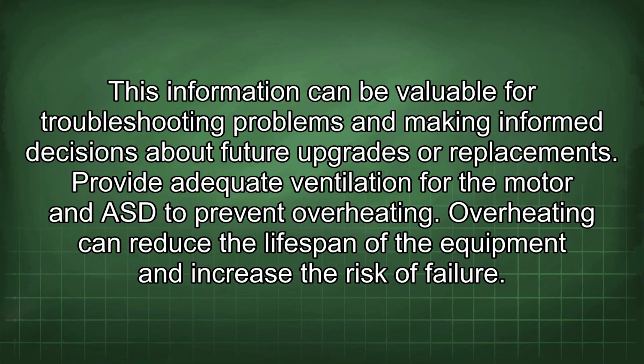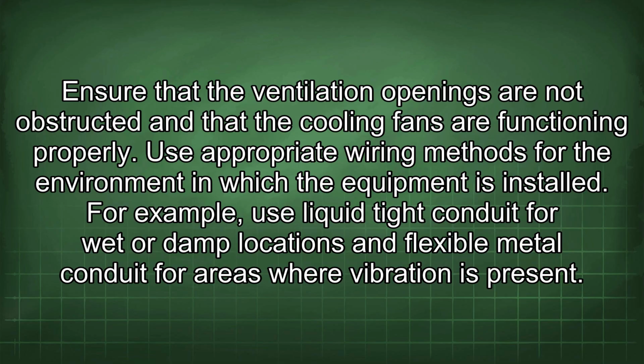Provide adequate ventilation for the motor and ASD to prevent overheating. Overheating can reduce the lifespan of the equipment and increase the risk of failure. Ensure that the ventilation openings are not obstructed and that the cooling fans are functioning properly. Use appropriate wiring methods for the environment in which the equipment is installed. For example, use liquid-tight conduit for wet or damp locations and flexible metal conduit for areas where vibration is present.